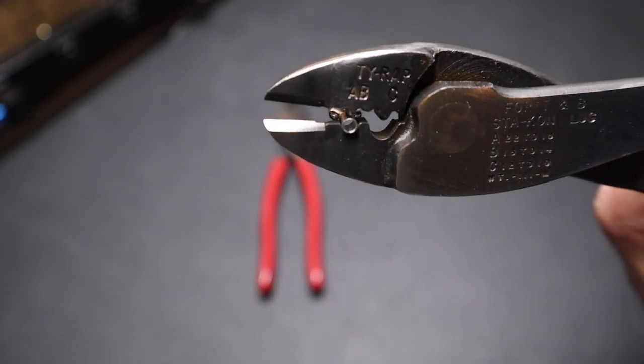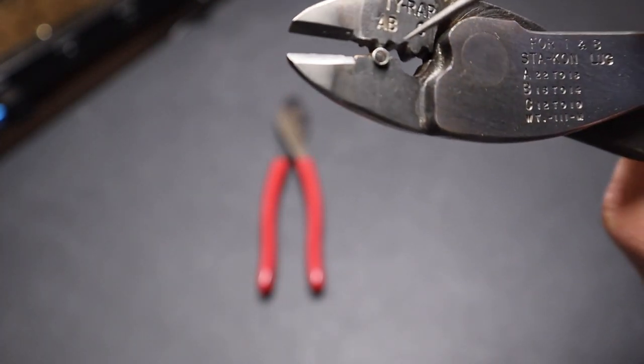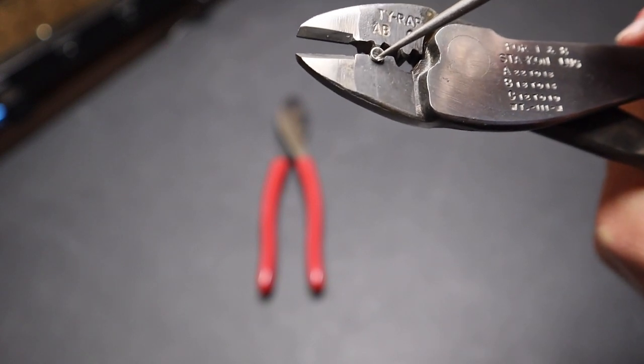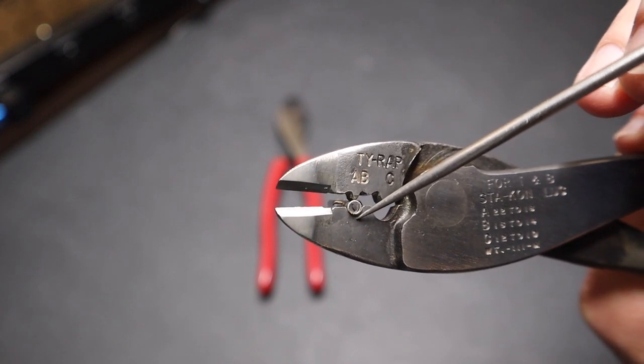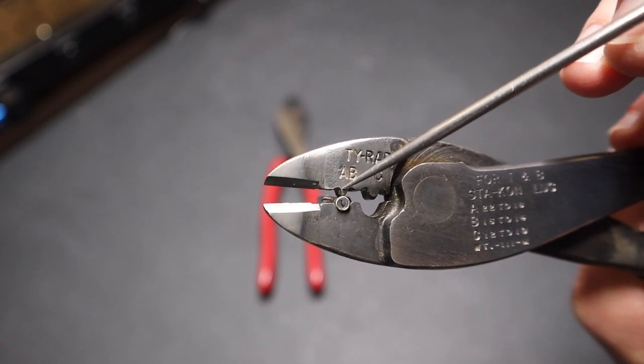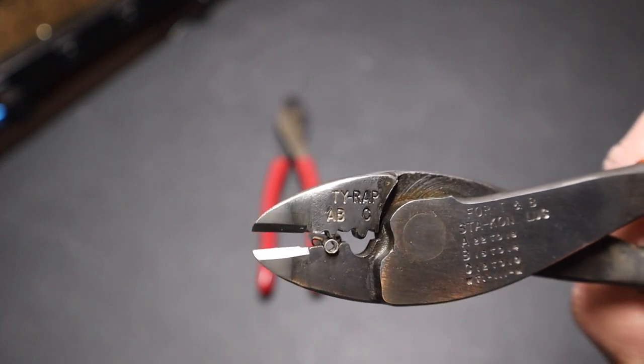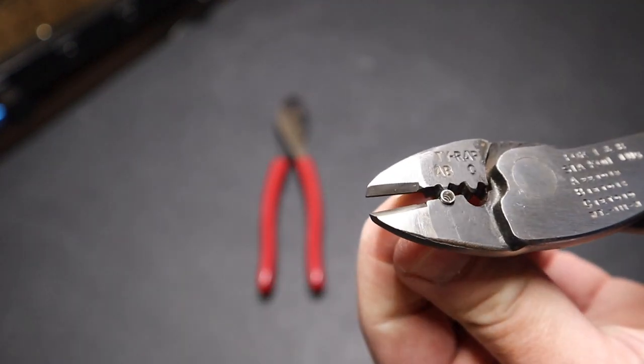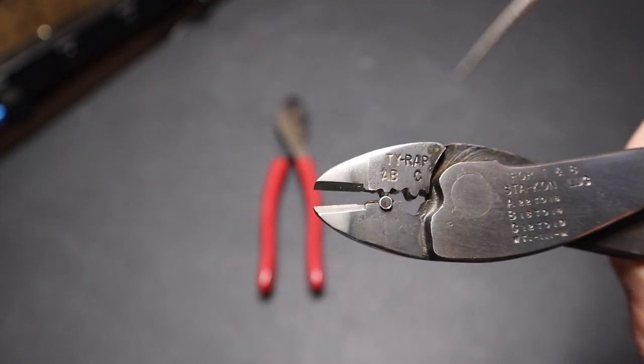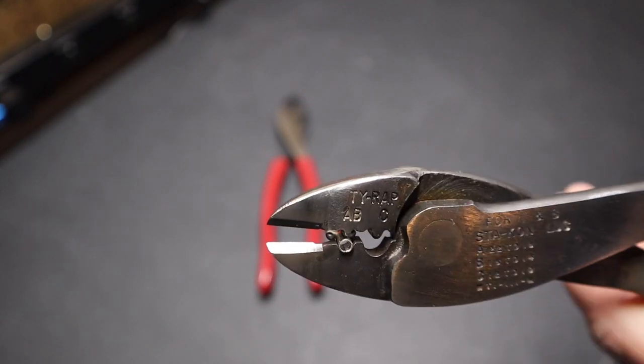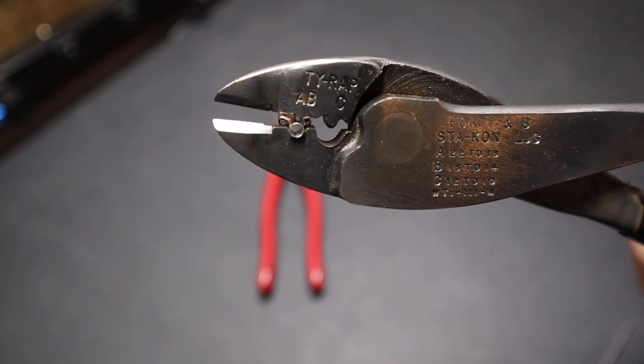I don't know if I can show that or not. I'll tilt it there, but this is actually split all the way down on the connector. And you want to put that in this trough part of the connector where I have it here at the bottom. You don't want it up here where the tooth is at. So you get your connection there. You try to center that part of that rolled steel down there in the bottom. And what you want to do is then just crimp down on it.